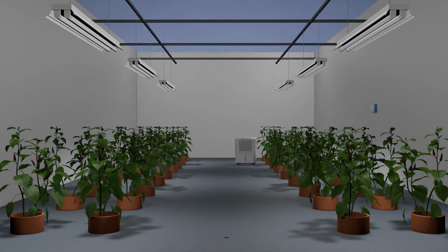Now, when it comes to controlling that humidity level inside of that space, it's not as simple as making sure that your percentage of humidity is right. It's also making sure that you are measuring that humidity level at the right place. The temperature of the air at the floor could be up to 10 degrees cooler than the temperature of the air at the ceiling. This is important because most dehumidifiers are hung from the ceiling in a growing space.